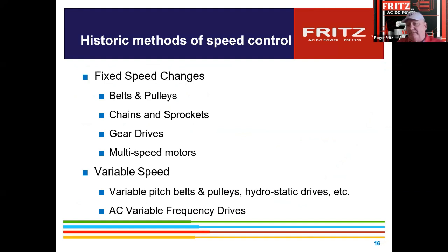The historic way of changing power and speed was done with belts, pulleys, sprockets, gears. We used to have multi two-speed motors. That's pretty much gone away, where they would shift the motor in the windings, and that would do a lot. We used to have variable pitch pulleys, eddy current drives on a big bunch of pumps that were out there. And then the implementation of the AC frequency drive.